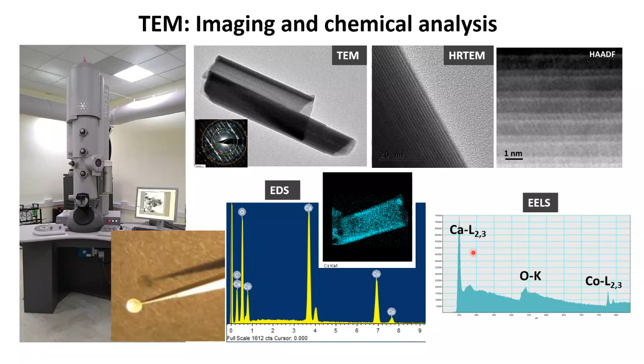Generally in TEM we can image in a bright field mode or a dark field mode. Basically, when you do bright field mode, you collect transmitted electrons and image them. Then your background is brighter than your sample. Or we can also do that in a dark field mode. In this case, the diffracted electrons are collected and imaged. You would have seen here the same sample at the same region, the contrast is inverted. Background is black in this case and your sample looks white because you are collecting diffracted electrons.